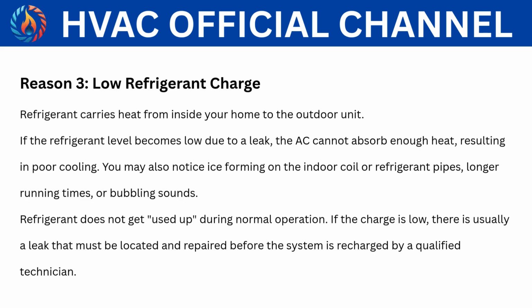Reason 3. Low refrigerant charge. Refrigerant carries heat from inside your home to the outdoor unit. If the refrigerant level becomes low due to a leak, the AC cannot absorb enough heat, resulting in poor cooling. You may also notice ice forming on the indoor coil or refrigerant pipes, longer running times, or bubbling sounds. Refrigerant does not get used up during normal operation. If the charge is low, there is usually a leak that must be located and repaired before the system is recharged by a qualified technician.